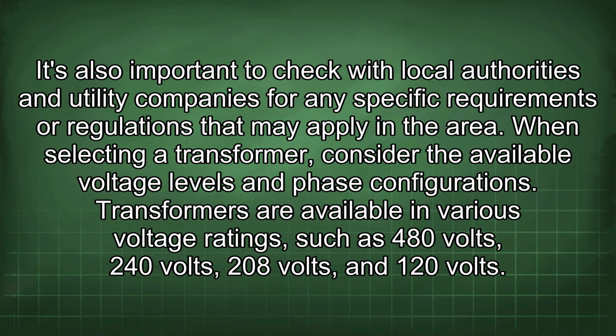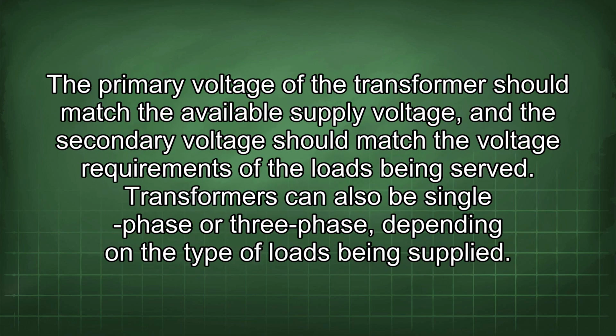When selecting a transformer, consider the available voltage levels and phase configurations. Transformers are available in various voltage ratings, such as 480 volts, 240 volts, 208 volts, and 120 volts. The primary voltage of the transformer should match the available supply voltage, and the secondary voltage should match the voltage requirements of the loads being served. Transformers can also be single-phase or three-phase, depending on the type of loads being supplied.